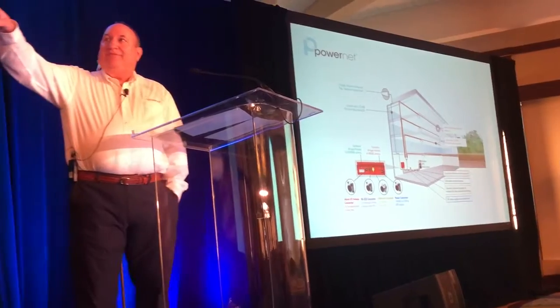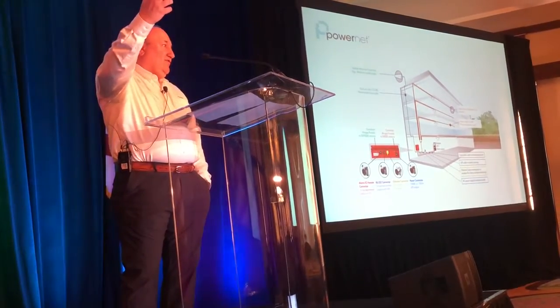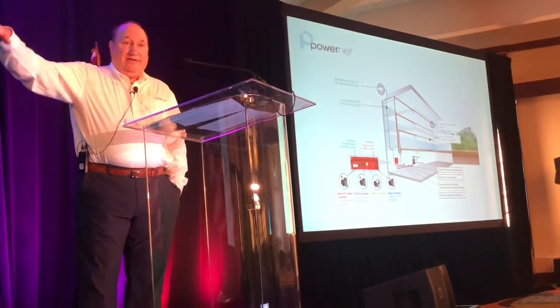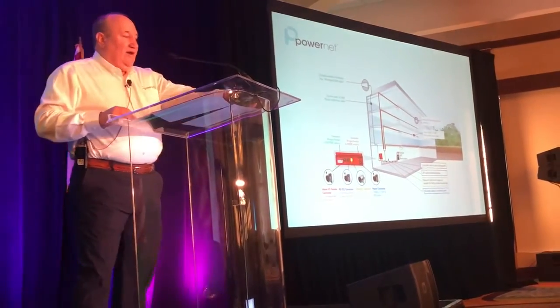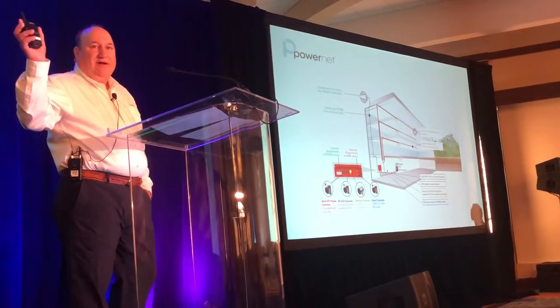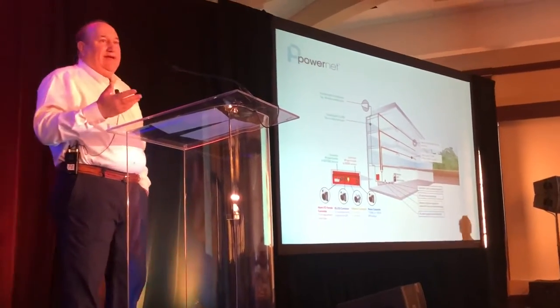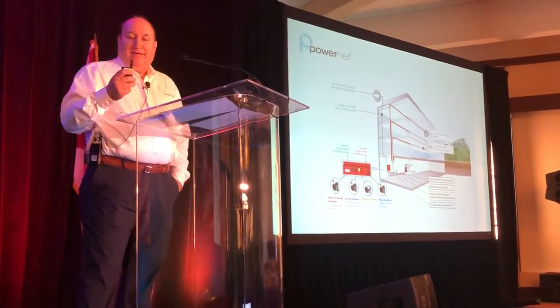All it does is, you'll see at the top left of that picture is an antenna that takes a signal from outside your building and brings it into an FCC approved amplifier that then distributes that signal throughout your building, so that you have a consistent signal level throughout your building for firefighters when they come in. Firefighters use a two-way radio system, and they are responsible for signal outside your building. But you are responsible for the signal coverage inside the building. There are specific things mandated by code that you have to do for your building for signal coverage, so we'll talk about that as well.